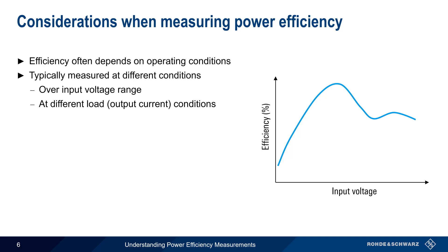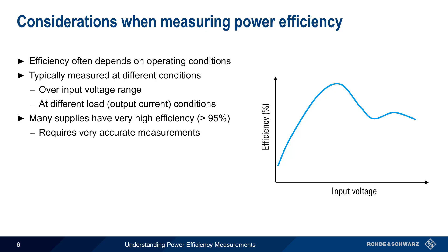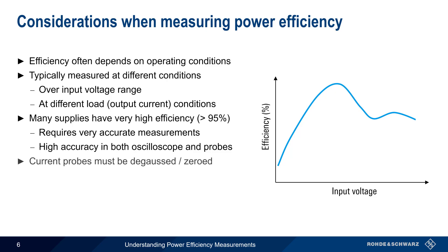It's important to remember that many modern power supplies have very high efficiency, so accurate measurements of voltage and current are needed to determine the very small difference between output and input power. Therefore, the oscilloscope and the probes used in power efficiency measurements should be both highly accurate and have the lowest possible noise. As with other current measurements, the current probe should be properly degaussed and zeroed, and the voltage and current probes should be properly deskewed in order to obtain precise power values. Please see the separate presentations on current probes and deskewing if you'd like to learn more about these topics as well.